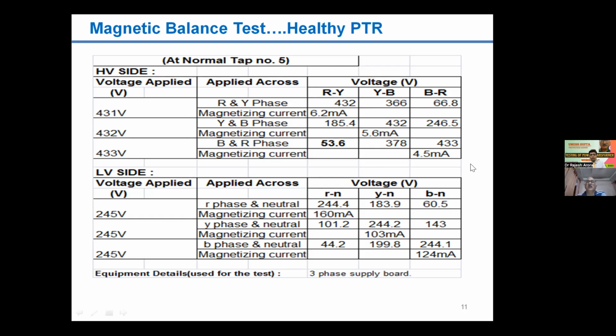depending upon the conditions. The same test is also done from the LV side. On the LV side, because the transformer is star connected, a single phase to neutral is injected, in R phase to neutral. As you see, the RN voltage of 240 volt is compared with the induced voltage in the two windings, YN and BN, and the magnetizing current is recorded. You may see that there is some symmetry in all the results. The magnetization current is also almost similar.